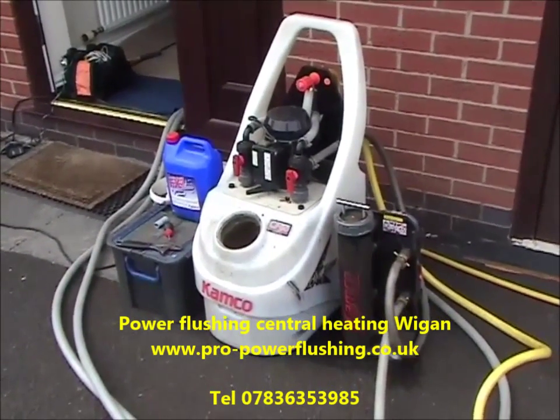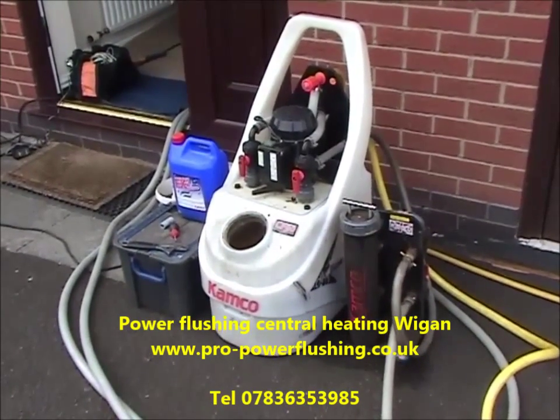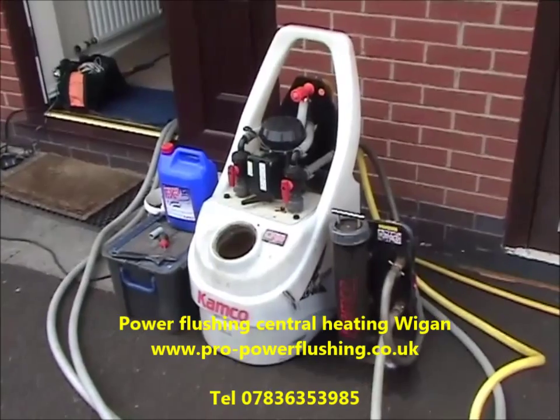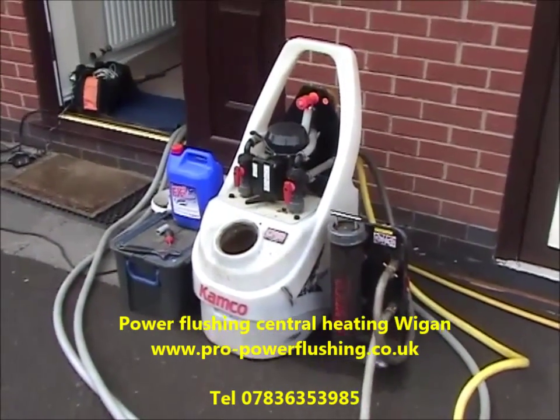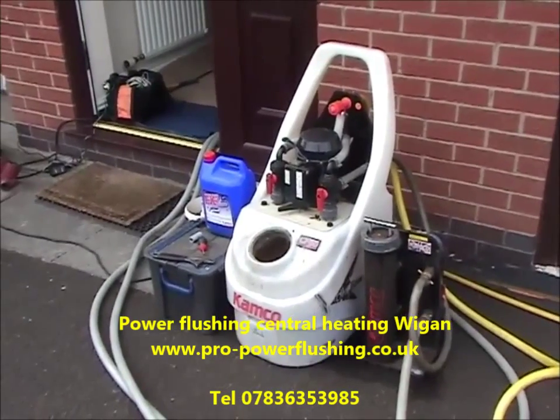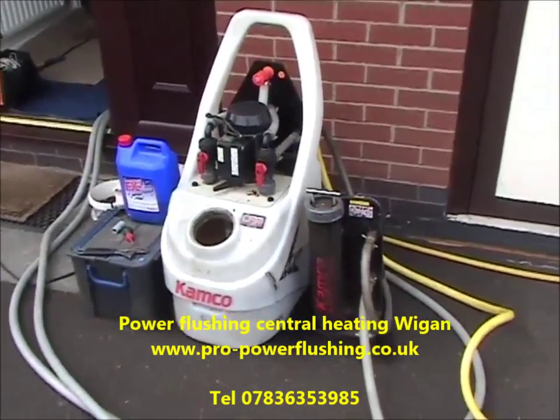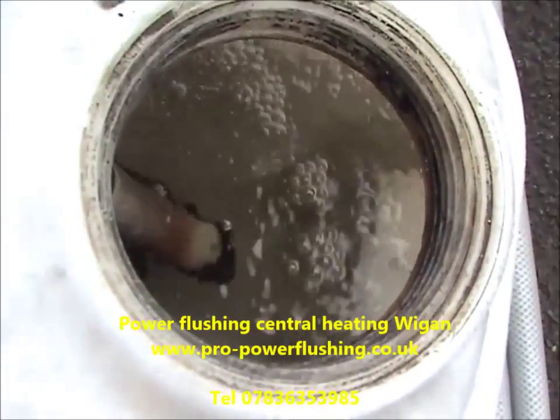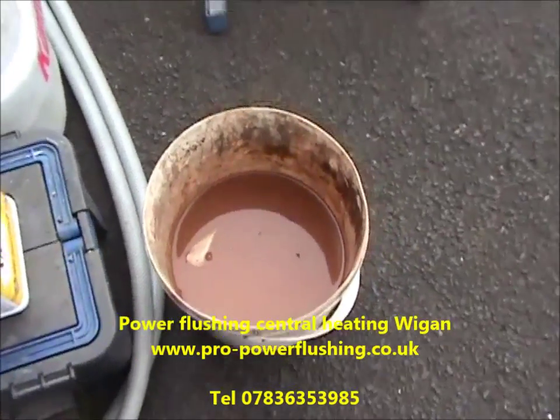Okay. Like we said before, we've already broken through these blockages on this central heating system. I know the job's a success before I've even finished the job today. We've still got a lot of cleaning out of the system to do. We've got to clean the header tank out, etc. So we're just going to get on with it, and we'll get back to you later. Okay, there's the header tank water, very rusty and sludgy. There's the water in the system now, getting nice and clean. We're on the rinsing process now.